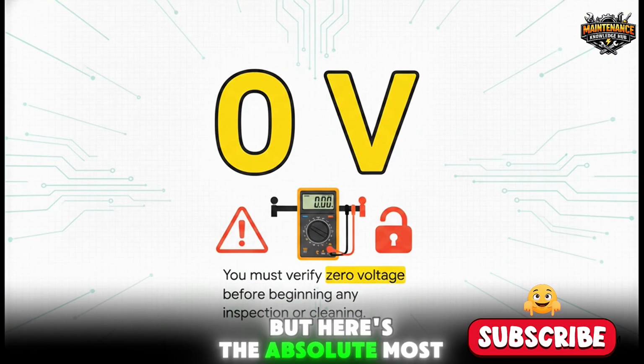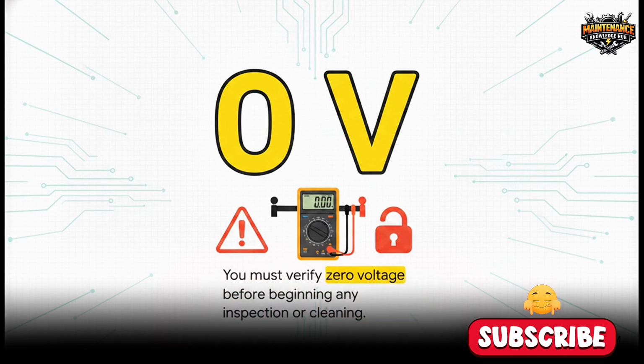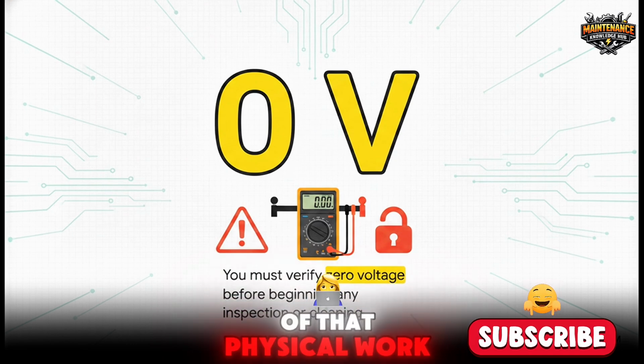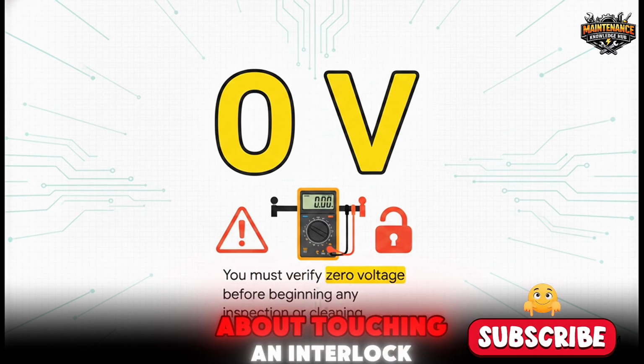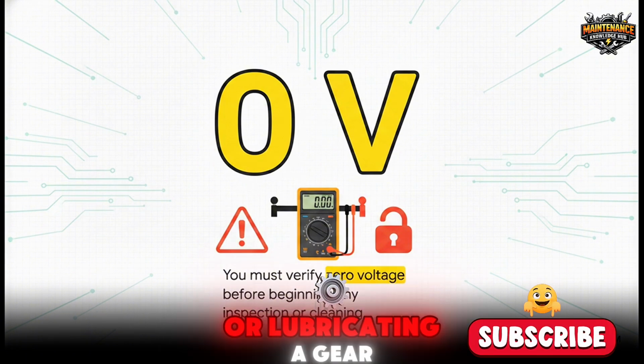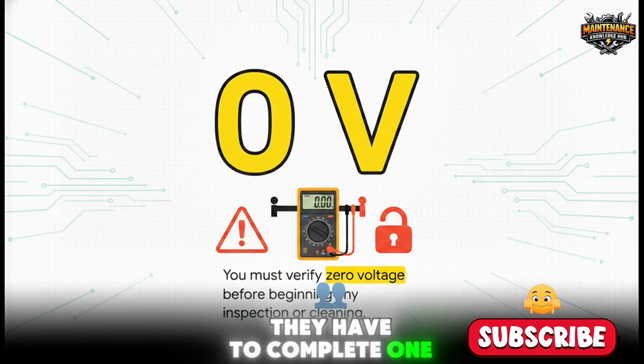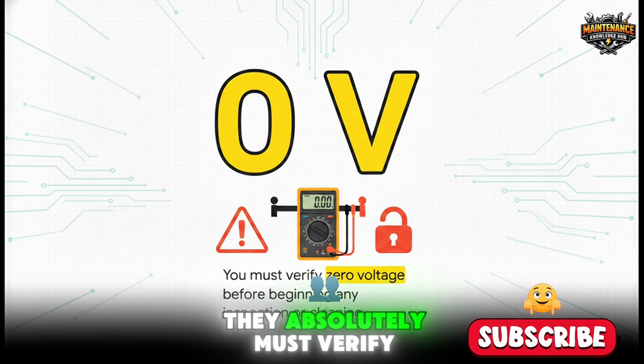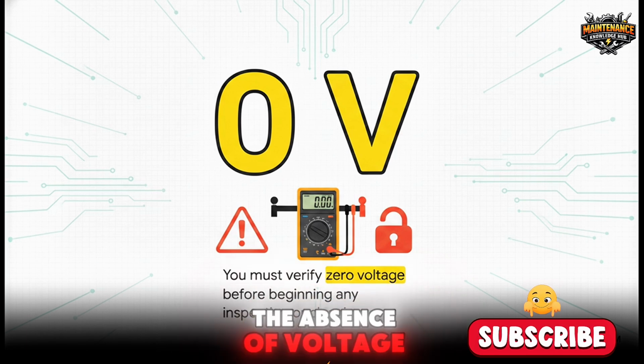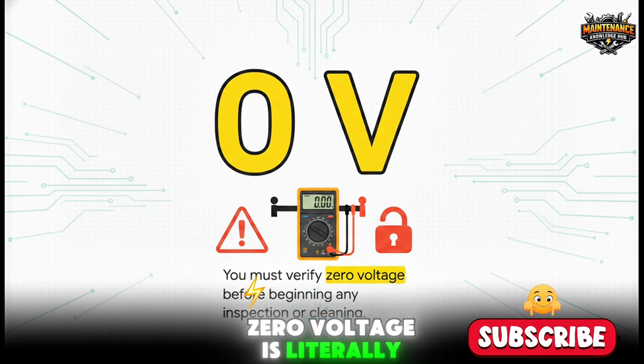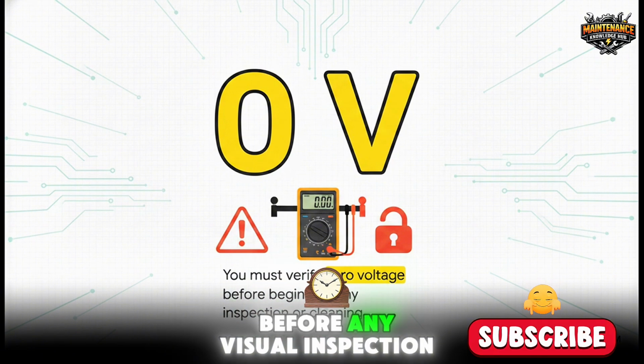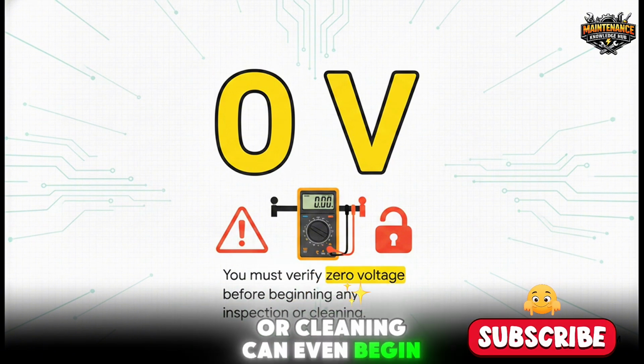But here's the absolute most critical point. Before anyone does any of that physical work, before a technician even thinks about touching an interlock, wiping down an insulator, or lubricating a gear, they have to complete one mandatory prerequisite: they absolutely must verify the absence of voltage. Zero voltage is literally the only acceptable number before any visual inspection or cleaning can even begin.